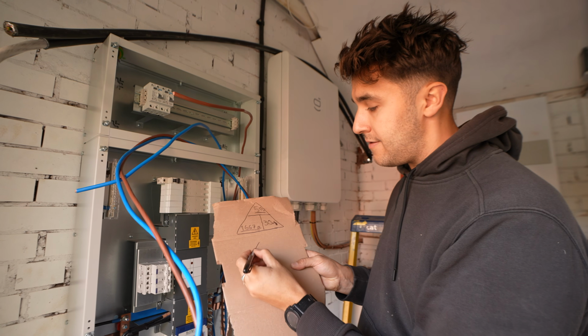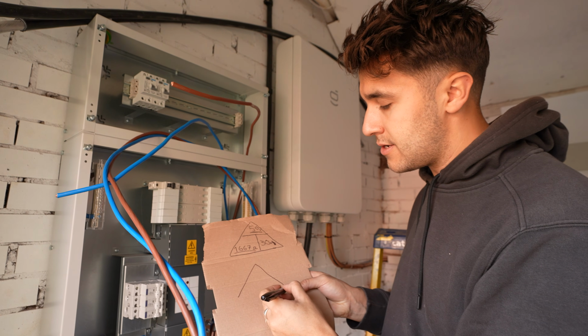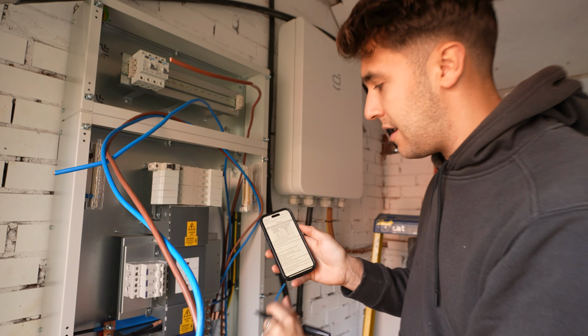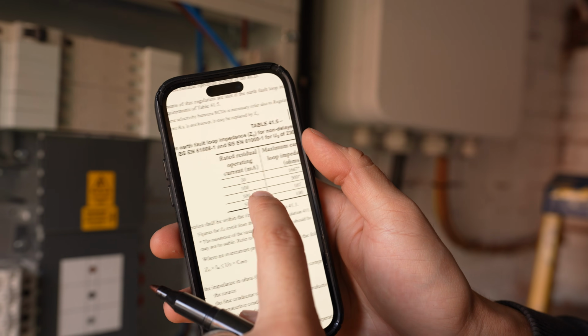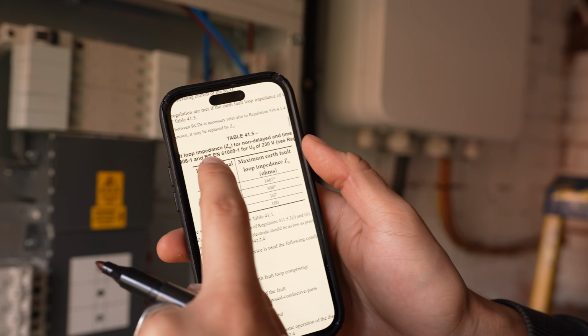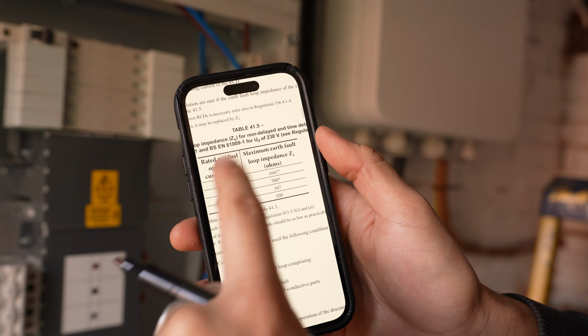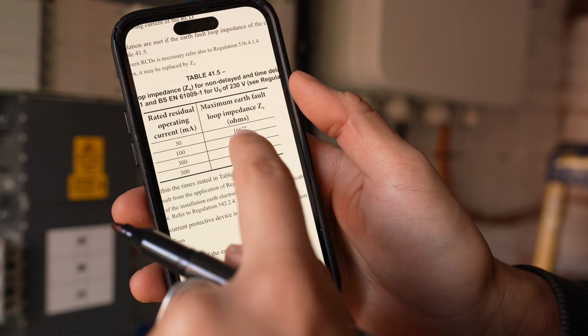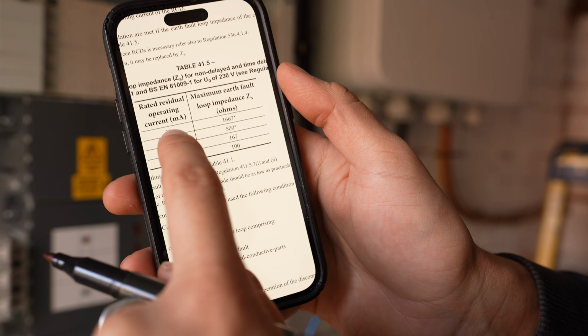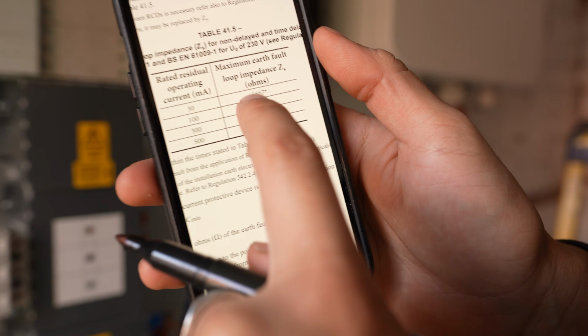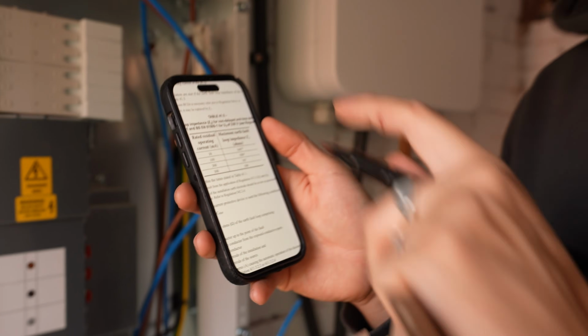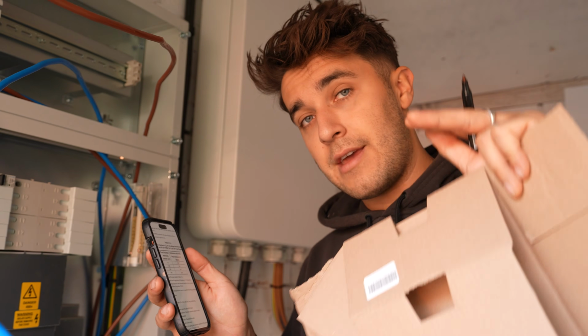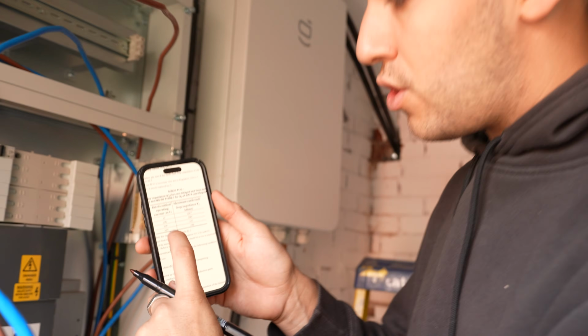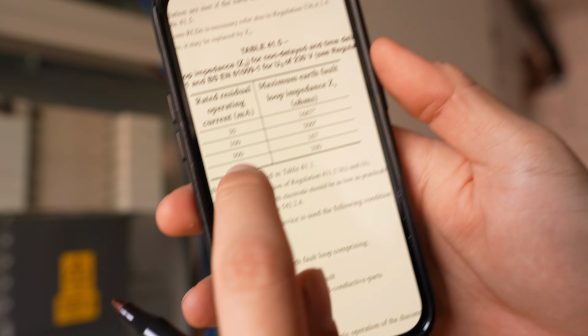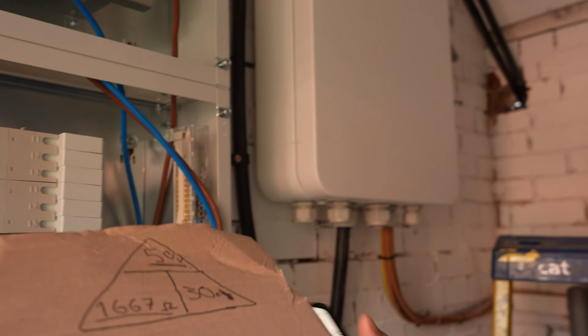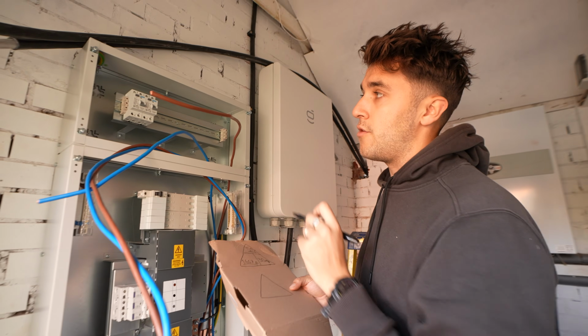Within the regs, you have table 41.5, which talks about maximum earth loop impedances for earth rods. As discussed, 1667 ohms is our max for a 30 milliamp device, but we can actually go higher because our earth rod readings are below 100 ohms. We could even go as high as a 500 milliamp RCD if we wanted.